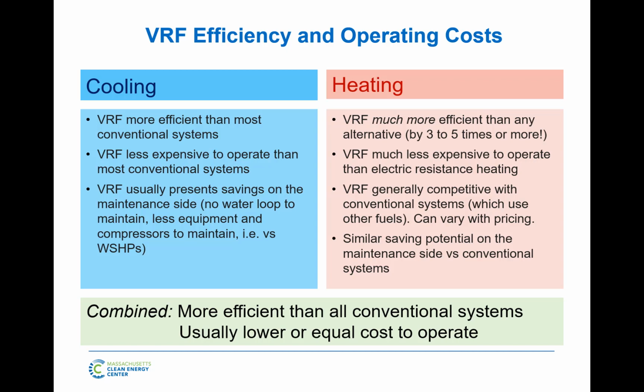In cooling mode, let's look at cooling only. VRF is essentially more efficient than any or most conventional systems. What that means is if you had a downtown Boston office building that's 30 stories and you were going to build a 5,000-ton chilled water plant with magnetic bearing chillers and VFDs on pumps and cooling towers, and you optimize that plant, very important, you can beat VRF at the end of the day.